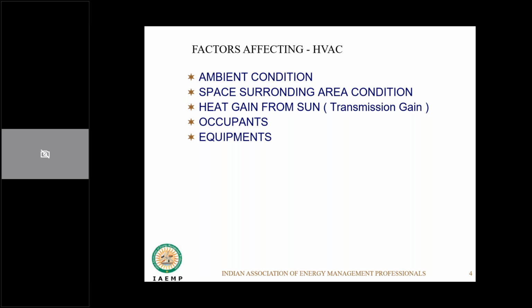Equipments. After transmission gain from the sun, the equipment at most times becomes a major source of heat gain. When I say equipment, your computer is equipment from the HVAC design perspective. It generates a lot of heat, and this has to be removed. If your office has a projector, that generates a lot of heat, and that has to be taken into account. And from an industry perspective, you have equipment and machines which are generating heat, like in labs, where you have a lot of series of equipment. While you're using them, they will generate some heat, because eventually whatever electric energy you put into your equipment gets converted into heat energy, and if it remains within the confined space of your air conditioning zone, you need to remove that. So equipment, understanding of that.